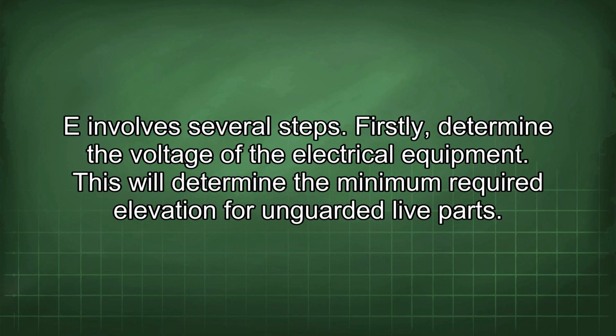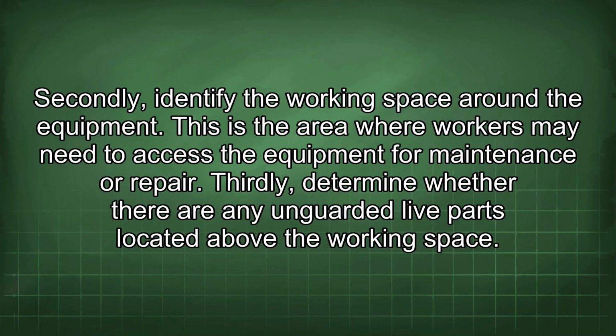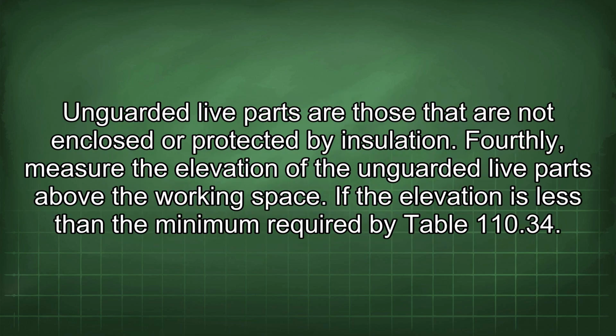Firstly, determine the voltage of the electrical equipment. This will determine the minimum required elevation for unguarded live parts. Secondly, identify the working space around the equipment. This is the area where workers may need to access the equipment for maintenance or repair. Thirdly, determine whether there are any unguarded live parts located above the working space. Unguarded live parts are those that are not enclosed or protected by insulation. Fourthly, measure the elevation of the unguarded live parts above the working space.